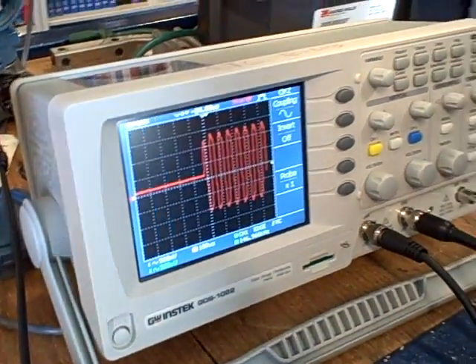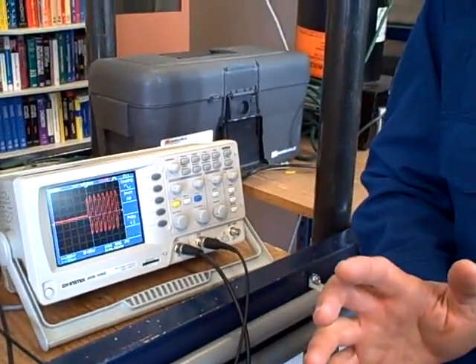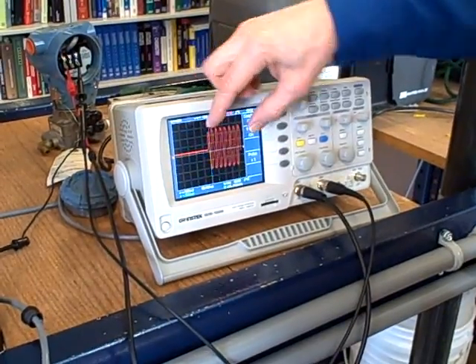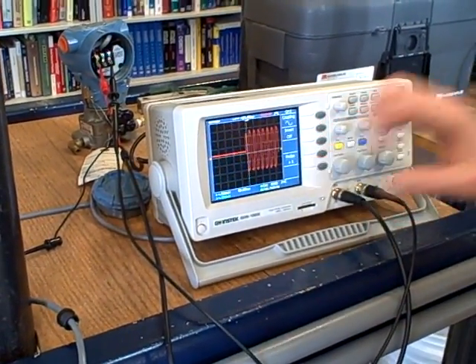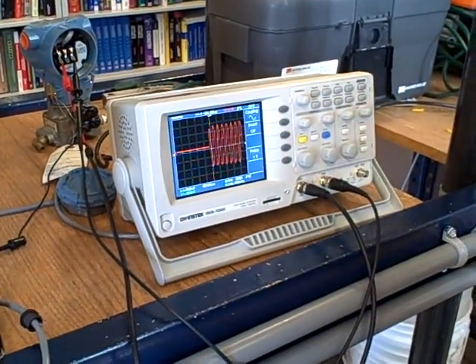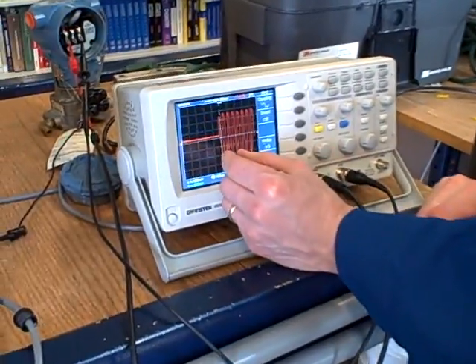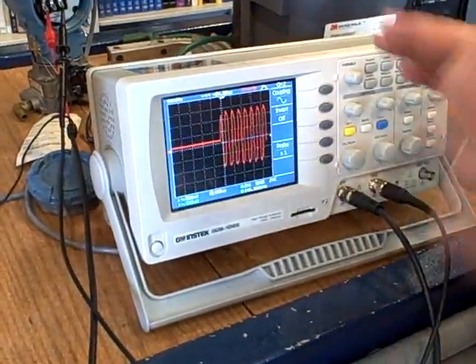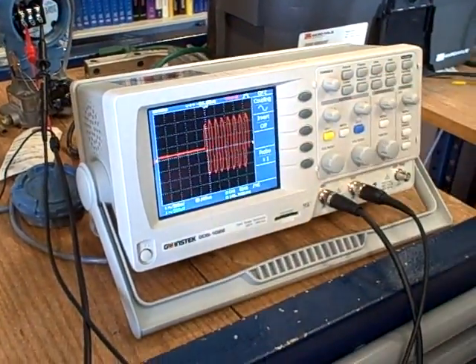You can see how this packet here begins with a nice symmetrical set of ups and downs. I don't know all the details of Foundation Fieldbus frame structure, but it looks to me very similar to how Ethernet is done, where you begin the frame with a preamble of ones and zeros. Every single field bus frame I've looked at with the scope begins the same way: a nice symmetrical series of ups and downs that are wide-spaced, meaning there are Manchester highs and lows, ones and zeros. And then after a sequence of ones and zeros, the real data begins.